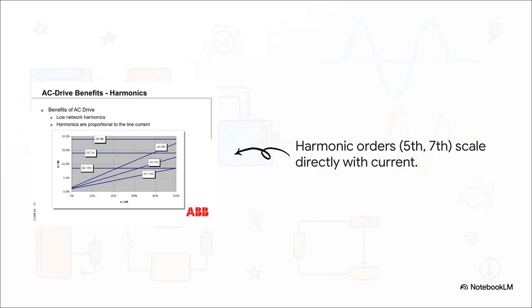So what's actually happening here? Well, a standard diode rectifier doesn't just draw a nice, perfectly smooth, clean sine wave from the ship's grid. Nope, it draws current in abrupt, non-sinusoidal pulses. And when you mathematically break down that pulsed waveform, you find these extra harmonic frequencies, specifically things like the 5th, 7th, 11th, and 13th orders, just stacked right on top of your fundamental 50 or 60 hertz grid frequency. These extra frequencies essentially circulate backward through the ship's electrical network, and if left unchecked, they cause unwanted extra heating and some serious interference with sensitive equipment.